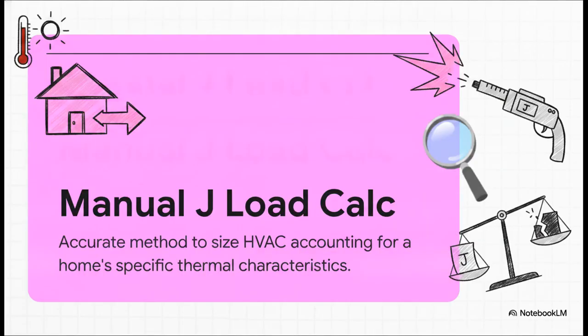To meet those strict standards, the only real weapon you have against getting the wrong size AC is demanding a real Manual J load calculation. This is the gold standard of the industry, literally the only scientifically accurate method to size an HVAC system, completely tossing that old lazy square footage rule of thumb out the window.